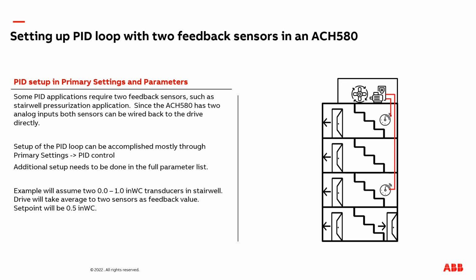Now, a common application where you'll need to connect two sensors to a VFD is a stairwell pressurization fan application. In the image on the right here, I've depicted a 4-story building with a VFD and motor on top, and a transducer on the 4th floor and one on the 2nd floor. In the following video, I'm going to teach you how to program the drive so it can be set up with both sensors connected to the VFD.